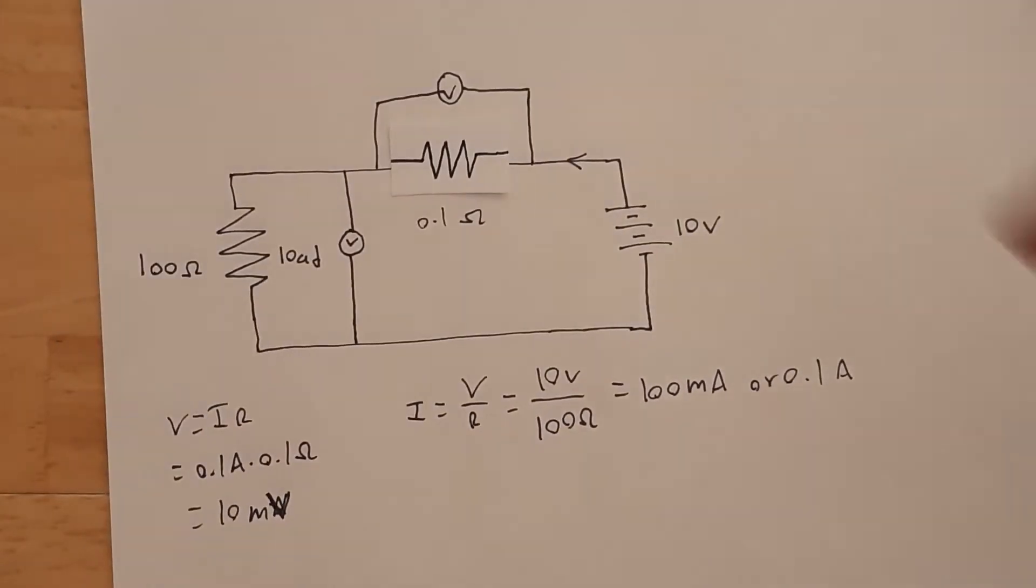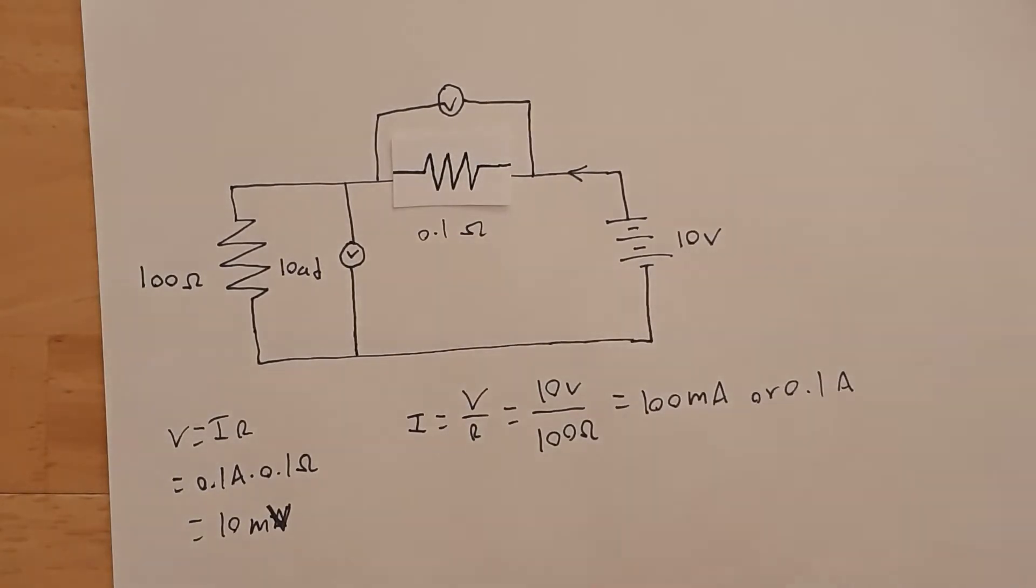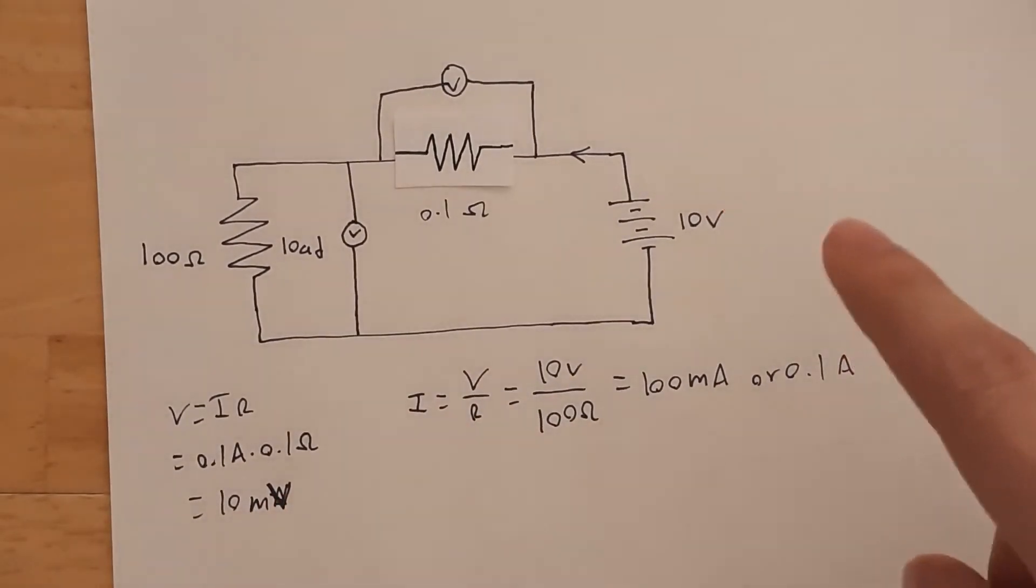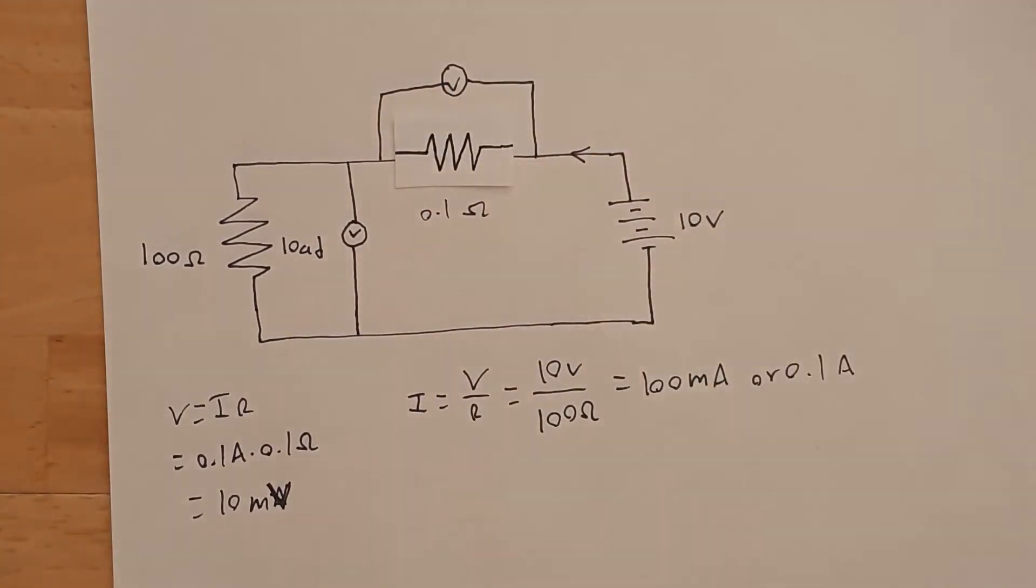We don't usually calculate that. We usually measure the voltage across this resistor. When we get a voltage, we convert that back into current by this equation right here again. We take the 10 millivolts, which is what we will see across this resistor, then divide that by the resistance of 0.1, then we'll get current.